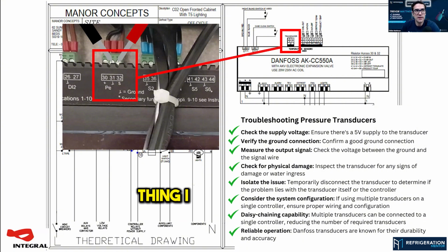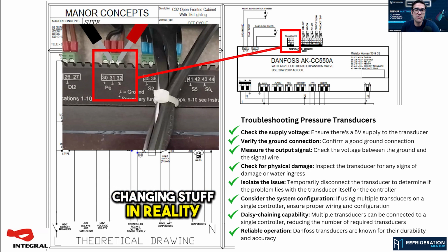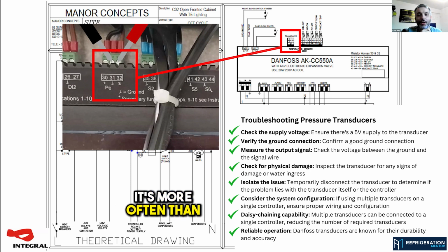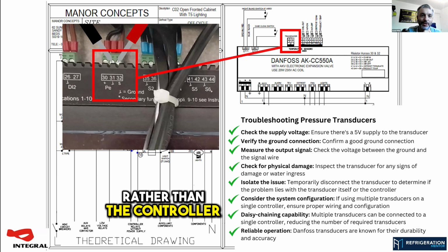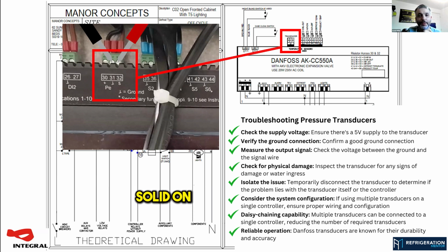Yeah. And that's a good thing. I didn't have the slide here, but that's exactly right. Pull it off. Am I getting the 5 volts out? If you are, then it's a transducer. And I've seen this countless times on CO2 systems where people are changing parameters, changing stuff in reality, or replacing components. In reality, it's just a pressure transducer that is faulty. Yeah, it's more often than not something it's using to calculate the superheat or the case temperature that's gone faulty rather than the controller. The controllers are pretty solid on things like that.